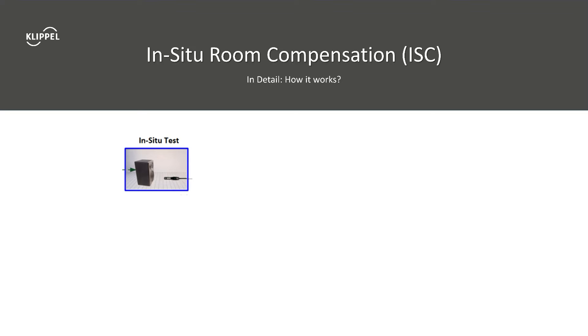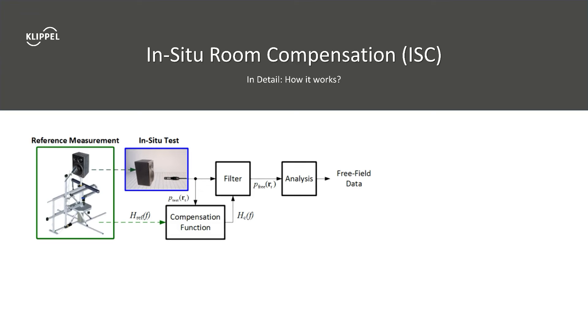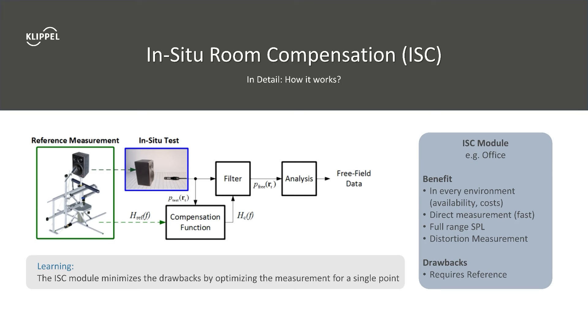The ISC is based on an acoustic measurement at a test position. This measurement can be performed in any room, like your office. By filtering the microphone signal with a compensation function, the influences of the measurement environment can be removed. This simulated free-field condition is the key for further analysis and diagnostics, either in time or frequency domain. The compensation function is based on a reference that can be gained in various ways.